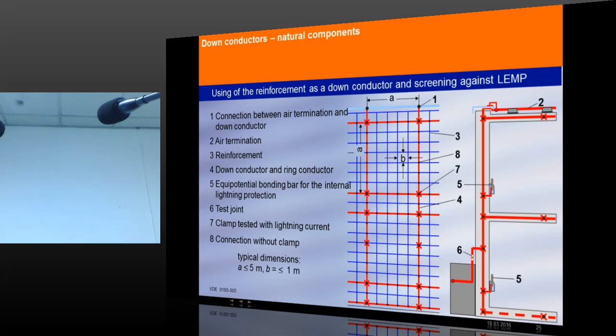So, now the most interesting point, number 5. Please understand, this picture is not my picture, it is from the standard, Part 4, from the standard SLS 147 Part 4. And now look at point number 5. Point number 5 is the equipotential bonding bar for the internal lightning protection.